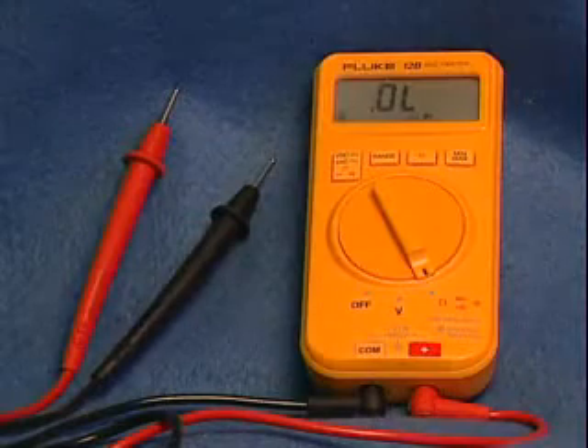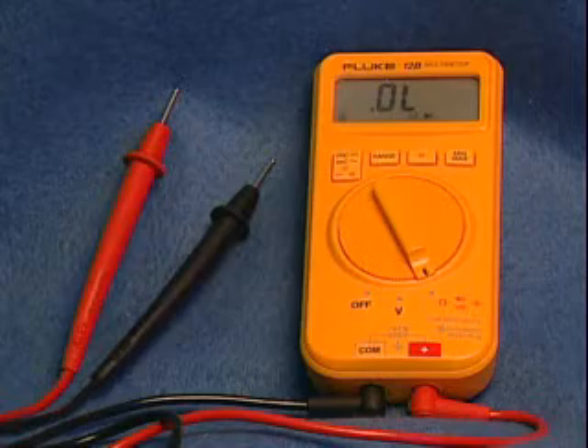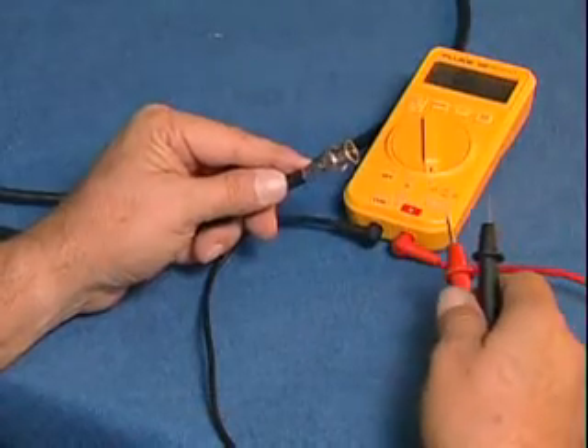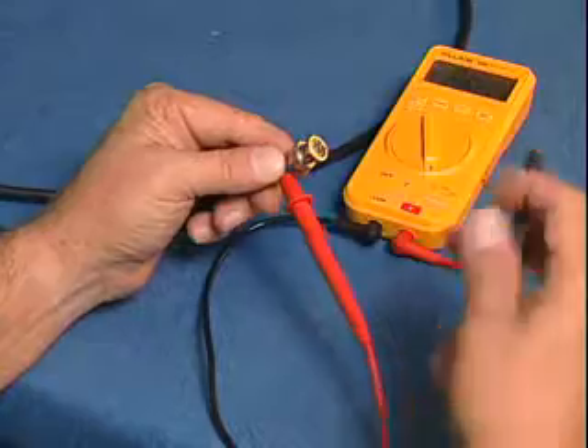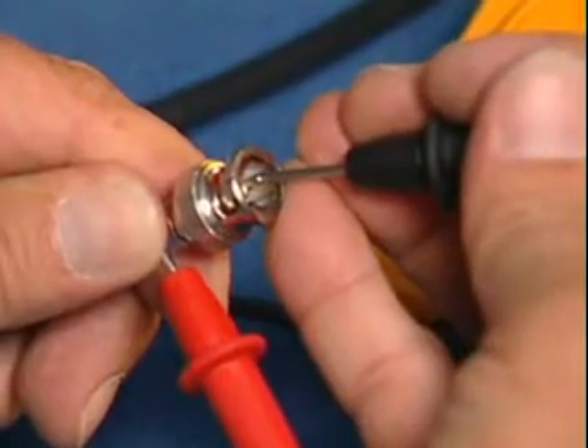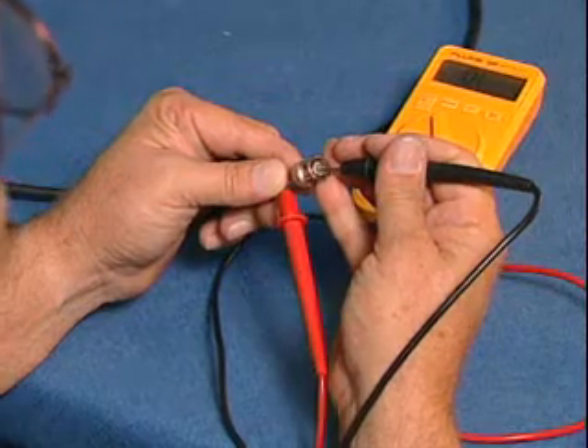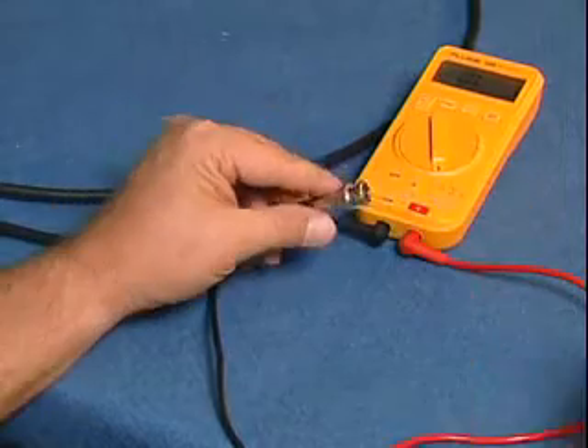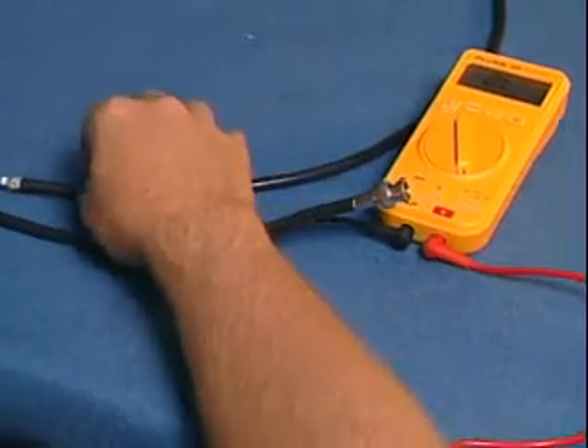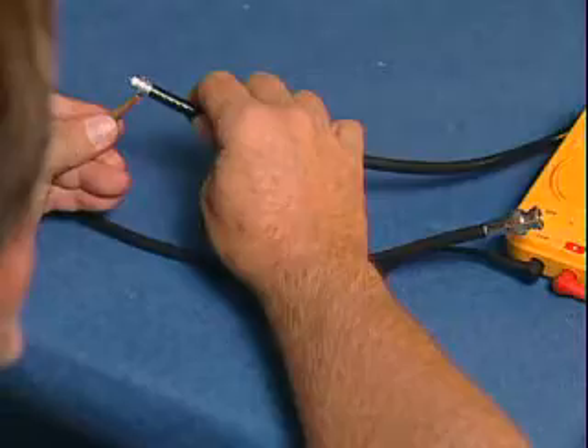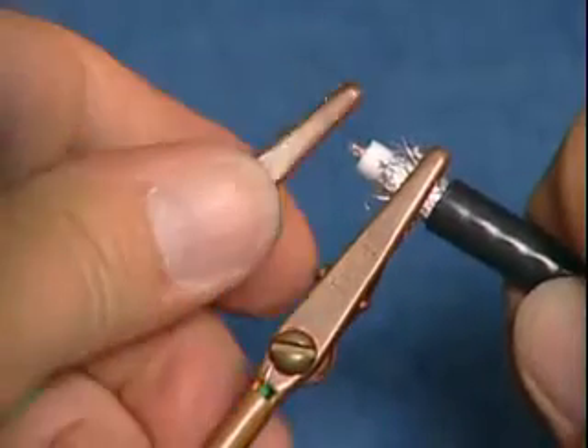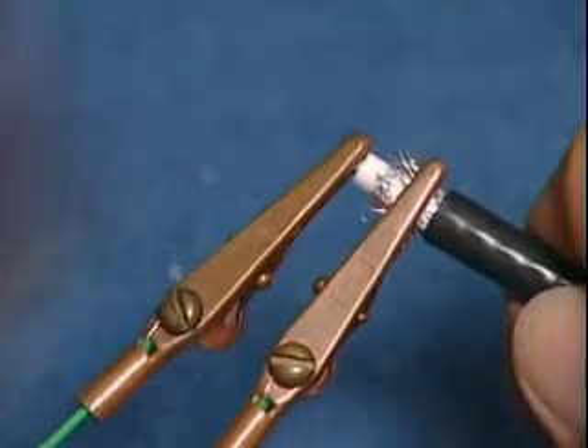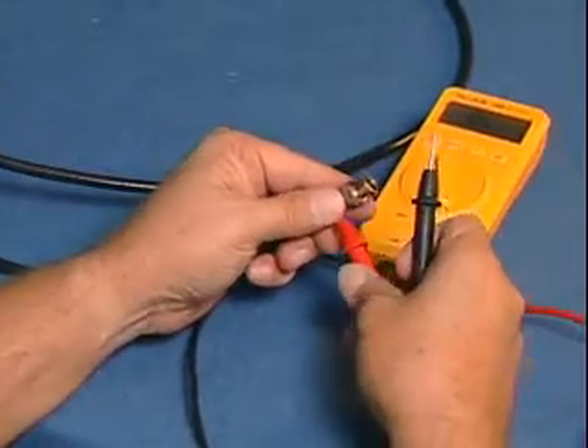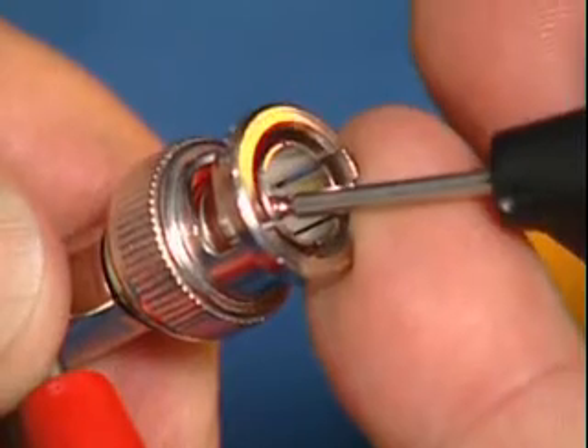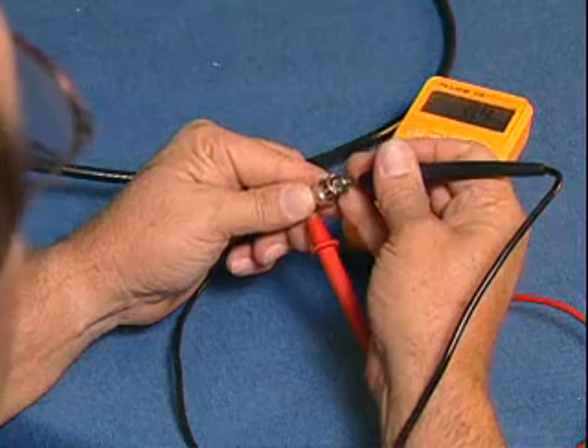A secondary method of testing is to use a multimeter. To test the cable and connector, first test for shorts between the connector body and the center conductor. Reading an open indicates a good cable and connector. Short the other end of the cable using a shorting clip and test the cable for continuity. Repeat the test between the connector body and the center pin. Reading a short tells us we have a good cable.